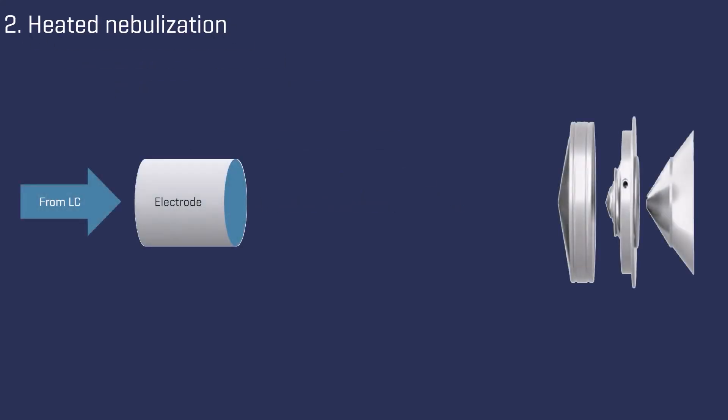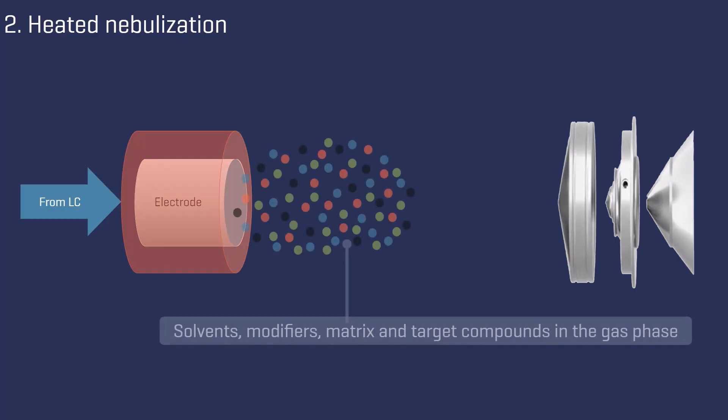In parallel, the liquid from the LC flow exits the electrode and enters the ion source. This area is effectively heated, causing the components of the LC flow — that is, solvents, modifiers, matrix, and target compounds — to be transferred into the gas phase.